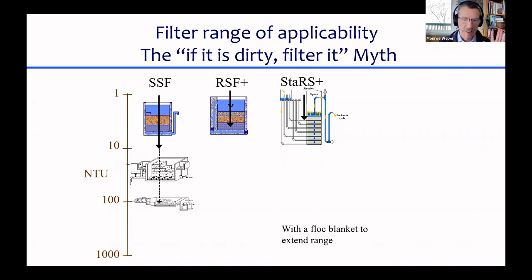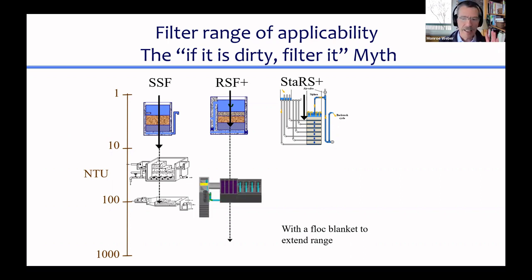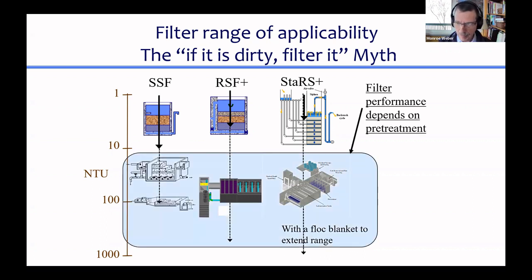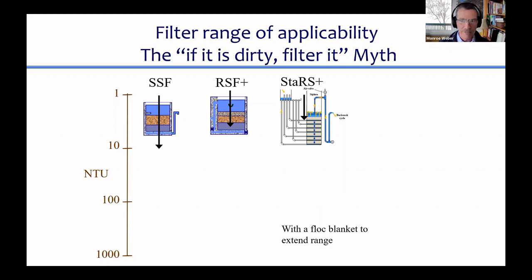For slow sand filters, there's multiple-stage filtration where gravel filters are added upstream to remove some particles. For rapid sand filters, flocculation and sedimentation are added upstream. For STARS filters, flocculation, floc filters, and plate settlers are added upstream. In all cases, filter performance varies depending on how clean the water is coming out of these pre-treatment steps. Filters are good for polishing water that is already pretty clean.